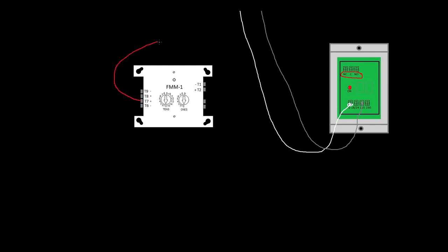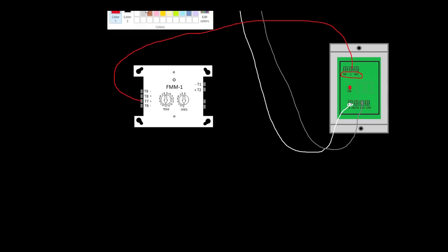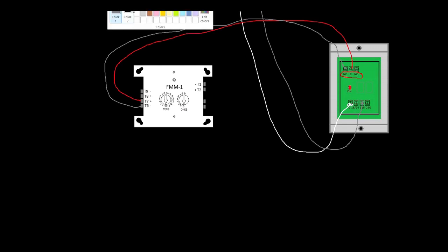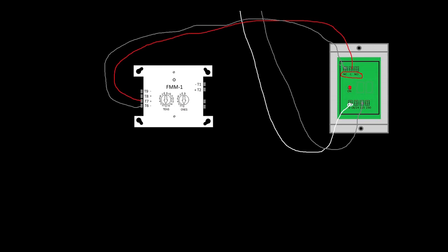All we're going to do is we're going to take terminals from T7, we're going to come into common, and then we're going to take terminal T6 and we're going to go to normally closed. Because while this relay is activated that's open, then we're going to take our resistor and land it across the pair.